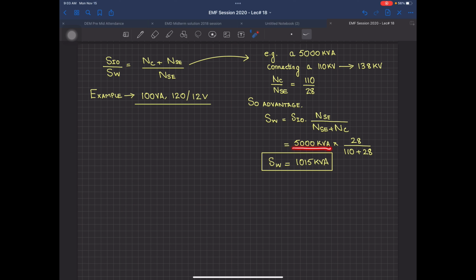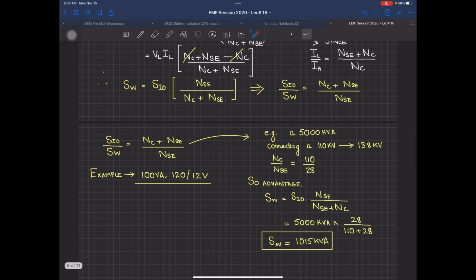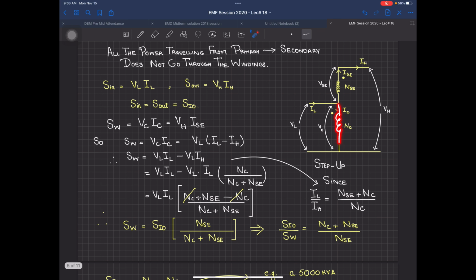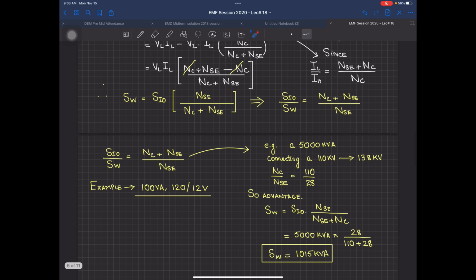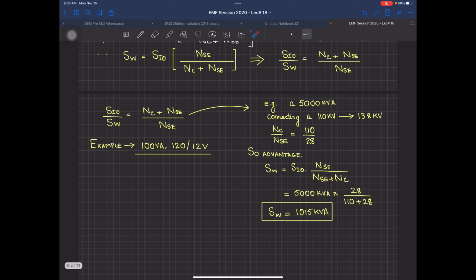So this will be 5000 kVA multiplied by 28 over 110 plus 28. You can see the advantage here: the series winding is going to be just 1015 kVA. If this is a step-up winding, this winding is just going to be 1015 kVA, while this winding is capable of 5000 kVA with only 28 turns.